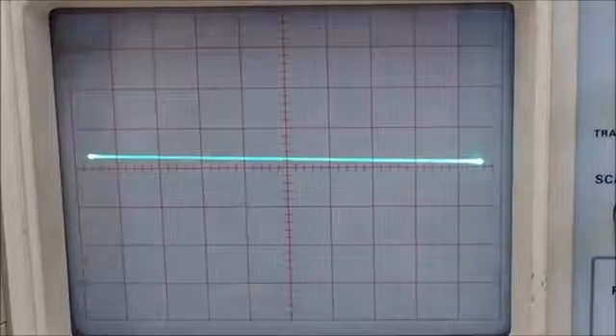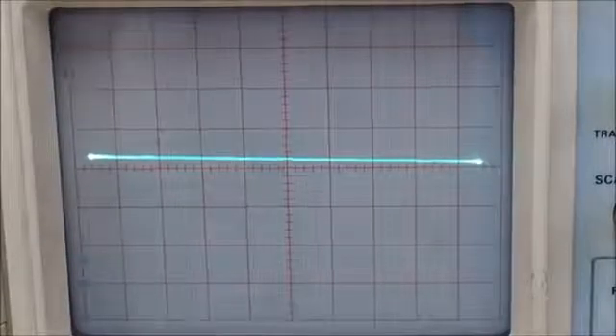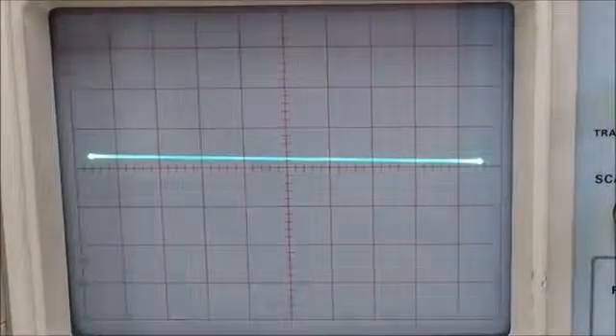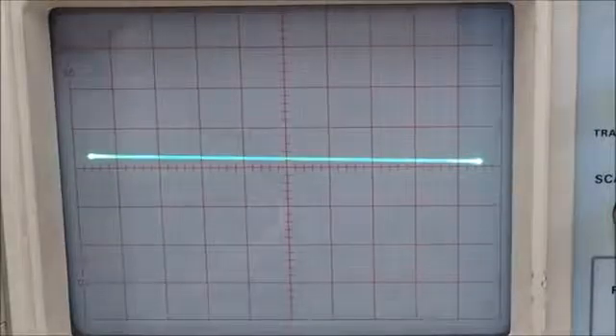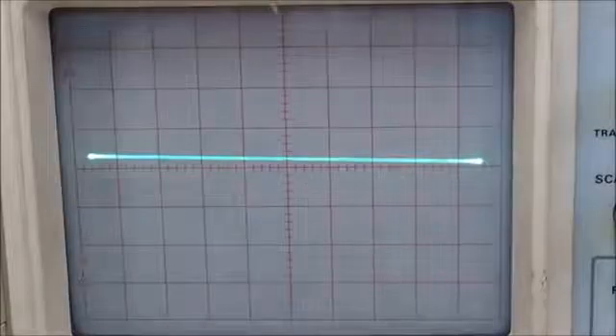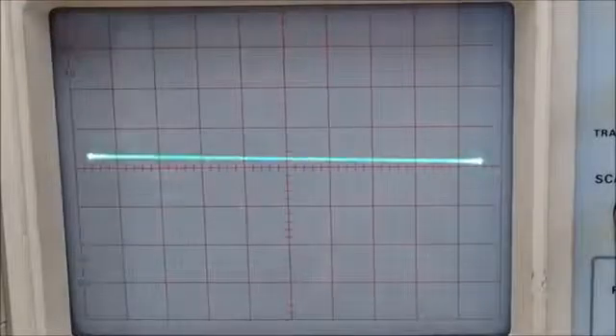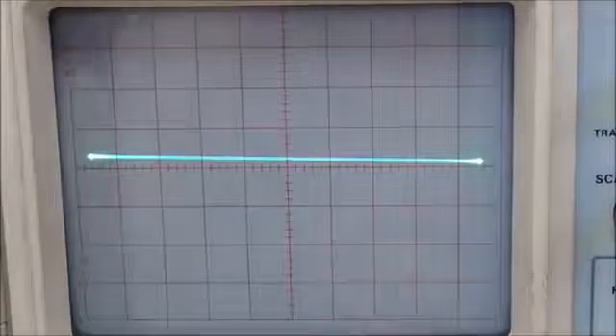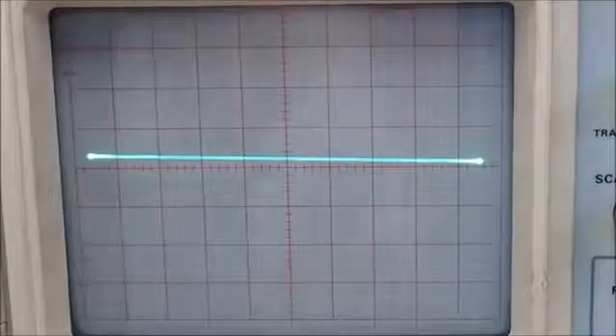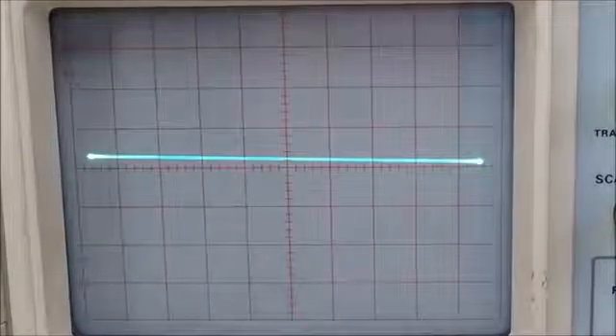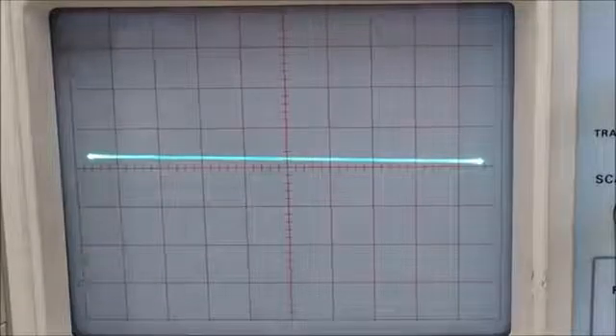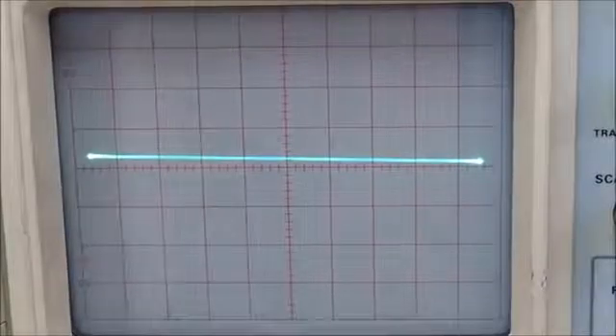Okay, so we've had a look at quite a lot of active and passive components. The last thing I'd like to have a look at is something that's known as a coax cable. It's got a PL259 on the end of it. And if we were to just have a look and see if the coax cable here is shorted, we can use the tracer quite easily to do that. I'm basically going to connect the centre conductors together, like that. Basically, I've got both centres connected. So now I know that we're shorting, as we expect to. But what about if I connect it to the centre on one end and the outer on the other? And, basically, we're seeing an open circuit image there, which tells me that we don't have a problem with this cable. And it's a good cable. So there you are. It's a good way of checking out cables as well. And, obviously, windings on transformers and motors, etc. If we want to have a look at those, we can do that as well.